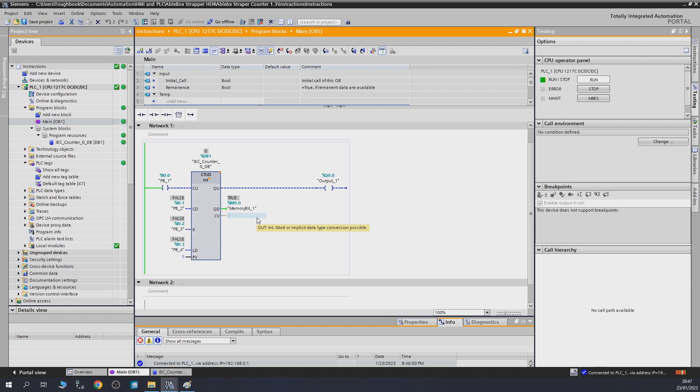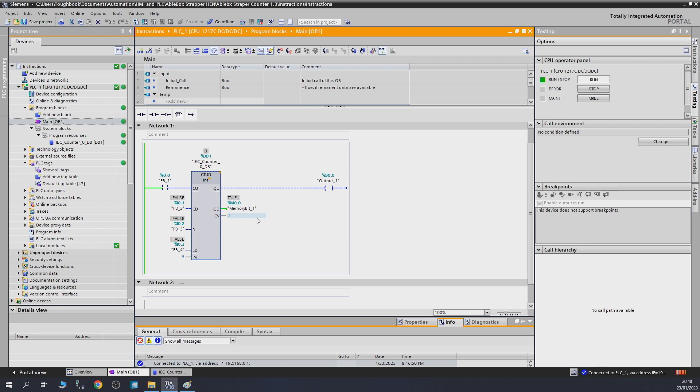If you count up, let's click push button one. As you can see, the state has changed, now both are off. I'll count it up, I'm clicking my push button one and it counted up. Once I reach five, as you can see, my output 0.0 has come on. If I click reset, obviously it will reset back down to zero, and as you can see my output down count is on now as well because it's gone down to zero. Let's say we go one up and then come back down again, and now as you can see my states are changing for the down count output.